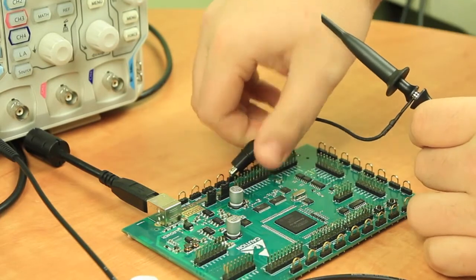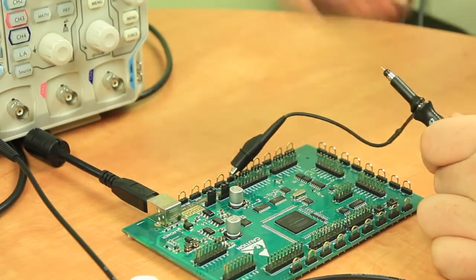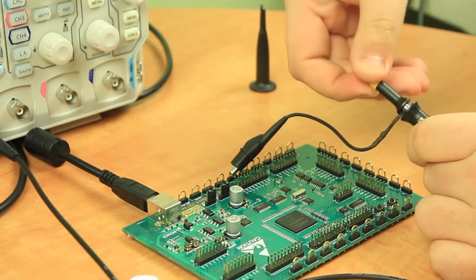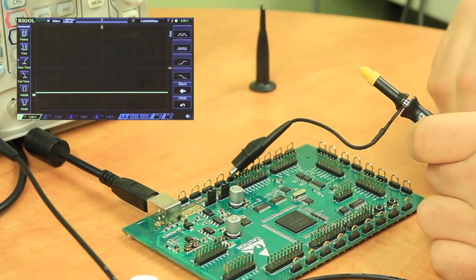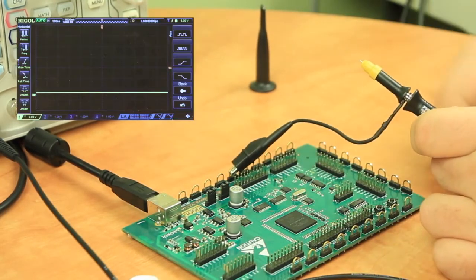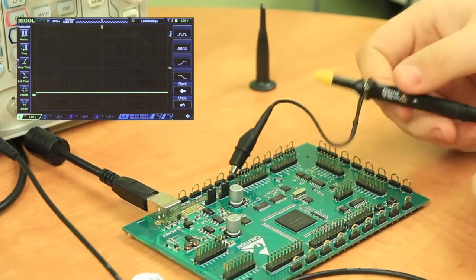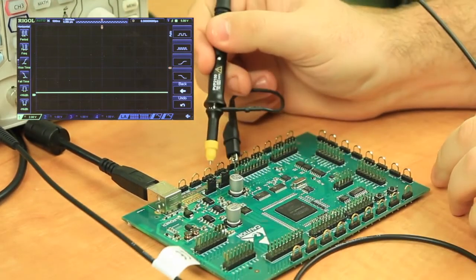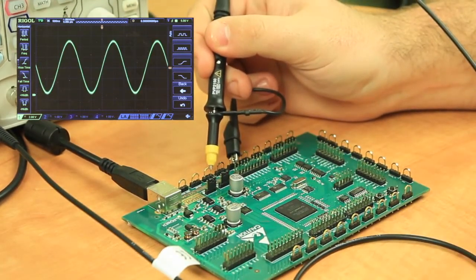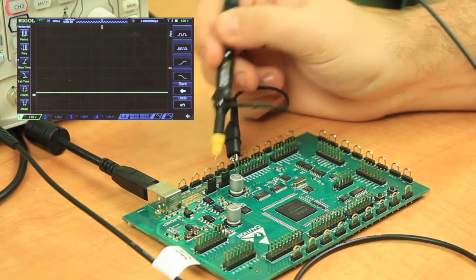Next, I'm going to disconnect the probe hook but leave the ground on. I'm going to take it off and push on the insulating cap. This is actually covering the ground on the probe itself, and now with this tip is where I'm actually capturing the signal. I'm going to capture the same sine wave with just the cap itself.